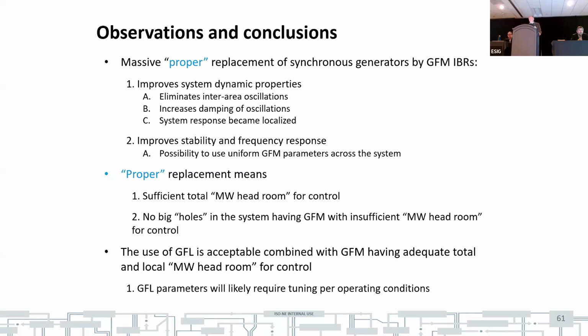And that is very important because it may have a very significant influence on the type of studies we do. Because before, we needed to study the whole system in order to reflect properties. If this conclusion is true, then you have drastically reduced the size of the area. And another observation is, as I said earlier, all parameters of grid forming inverters were exactly the same, no variation across the system. And that is a very good indicator that you don't need to be worried about tuning of parameters of inverters. You can take universal settings and apply them like an on-the-shelf solution for any location in the system.